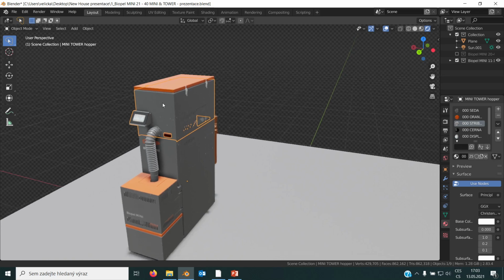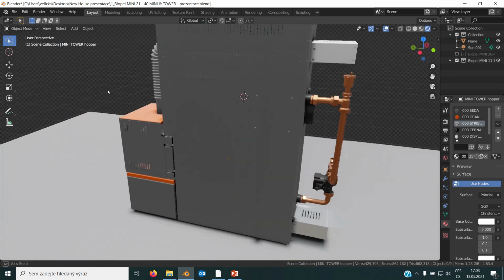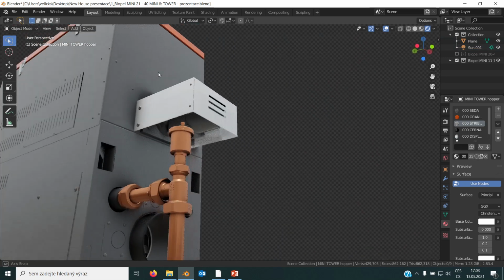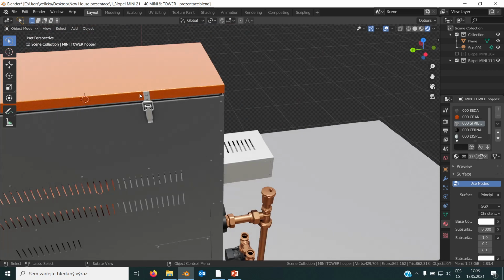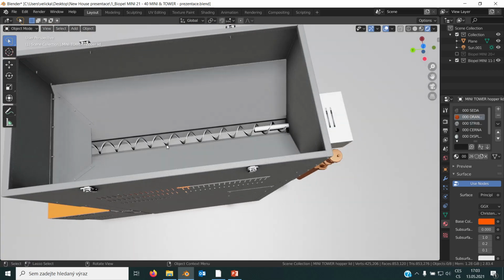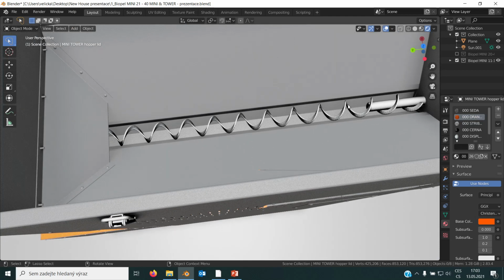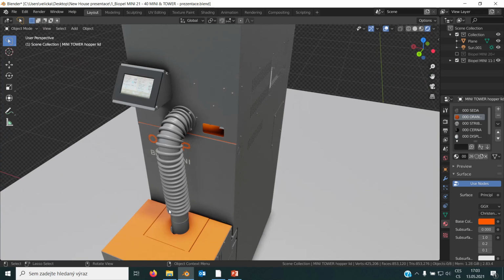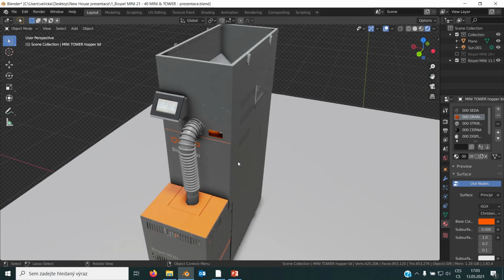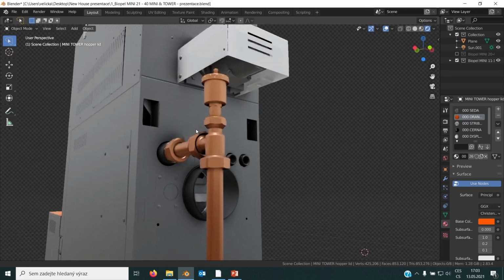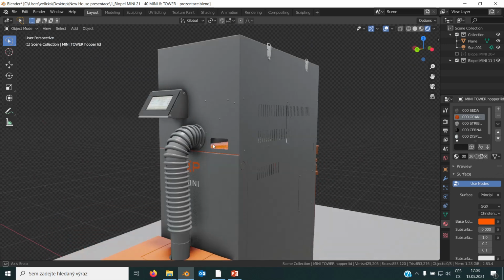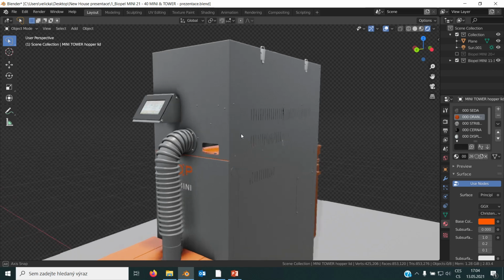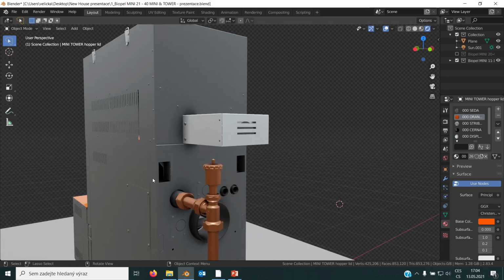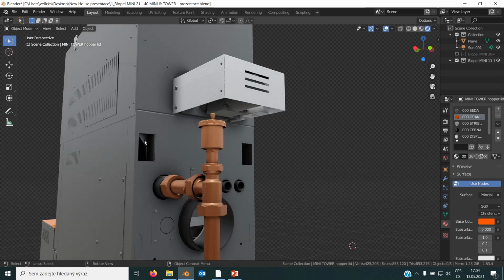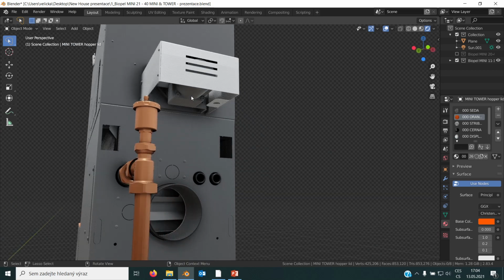When you install the pellet hopper, you just put it in place. From the back side there is a motor. Here we have a motor which moves the spiral which is inside. So this spiral moves the pellets from the hopper to the pellet burner, and of course you have to connect the power cable to the motor. So again, when you buy the boiler, the cables are hidden inside the control unit on the top of the boiler, and you basically move the cable from the control unit through this shaft to the back side of the boiler and then connect the cable to the motor here. Okay.